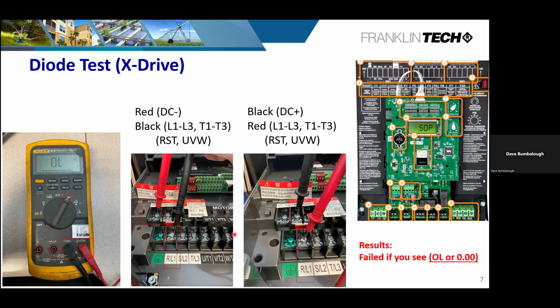And the output side is usually referred to as T1, T2, and T3, or UVW. Okay, now in the Americas, we refer to our line side as L1, L2, L3, and our outgoing side is T1, T2, T3. The European standard is RST for input, and then UVW for the output. Now granted, you may have a situation where it's a single phase in, right? So you'll just be dealing with L1, L2 and skip L3 because there's typically nothing hooked to that if you're using single phase coming in and you're using the drive to basically convert that energy to three phase.